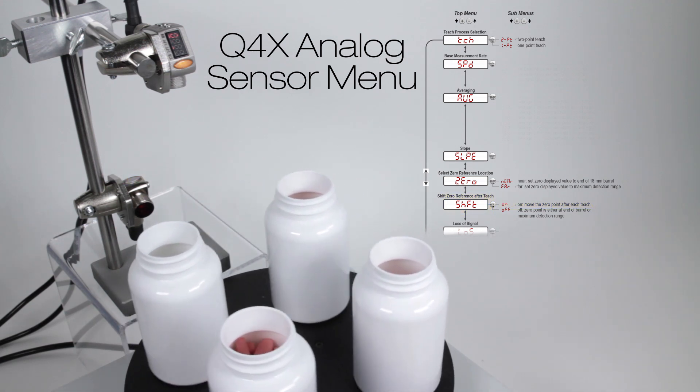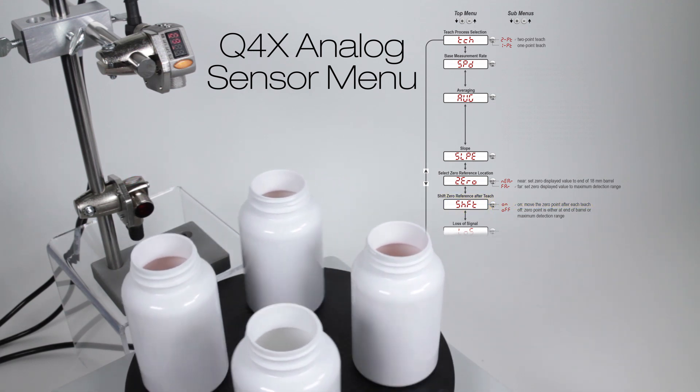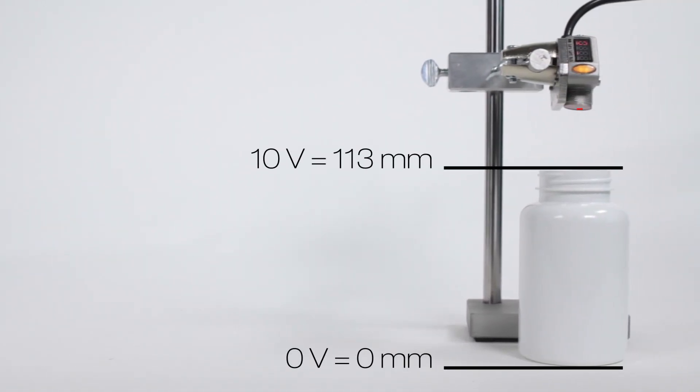With these settings, the display measurement will be relative to the zero-volt taught point. In this example, the bottom of the bottle is set as a zero-volt signal, and the top of the bottle will be a 10-volt signal.